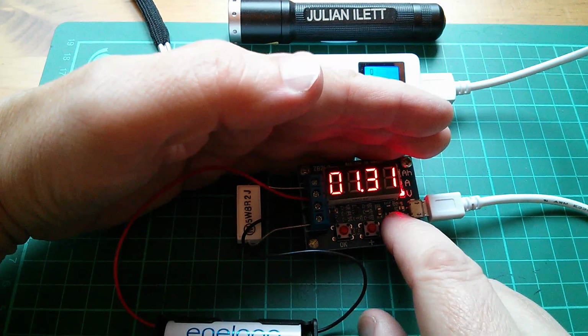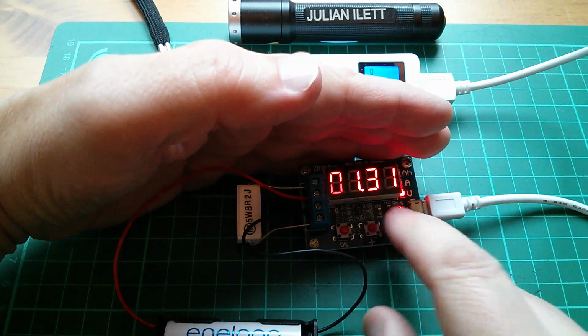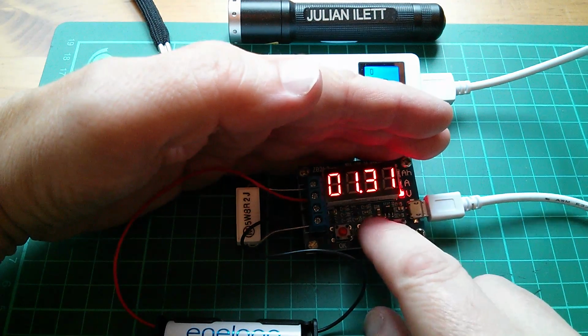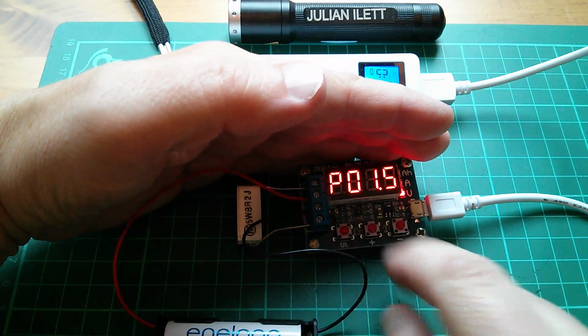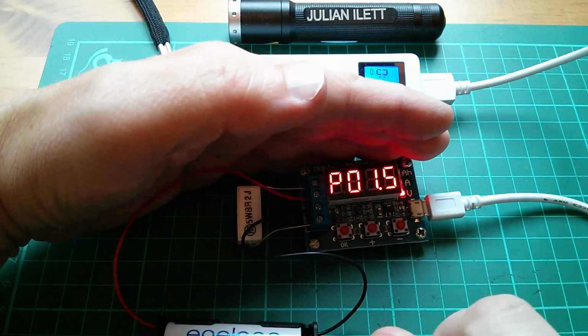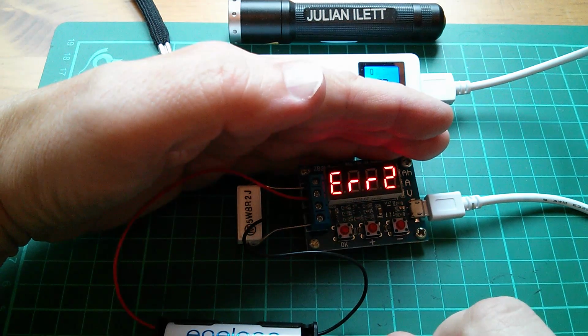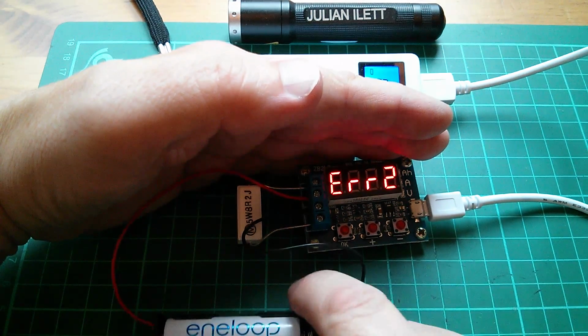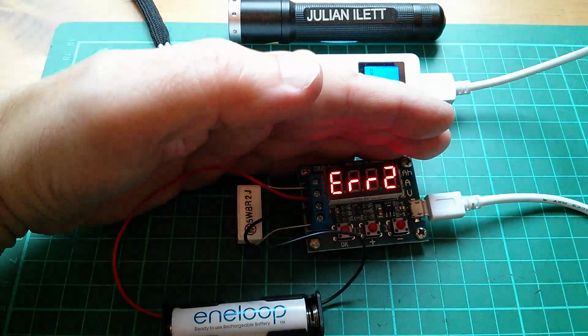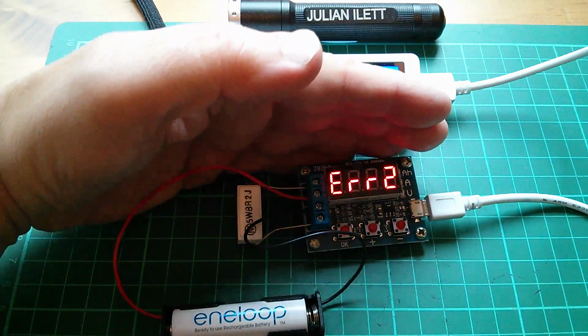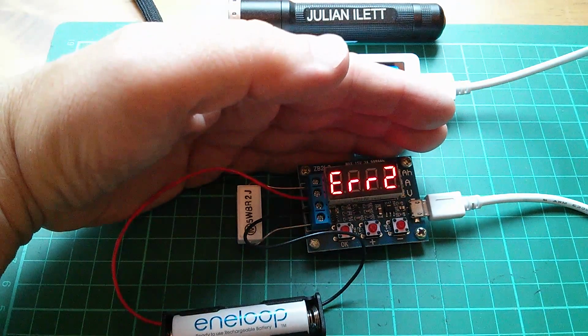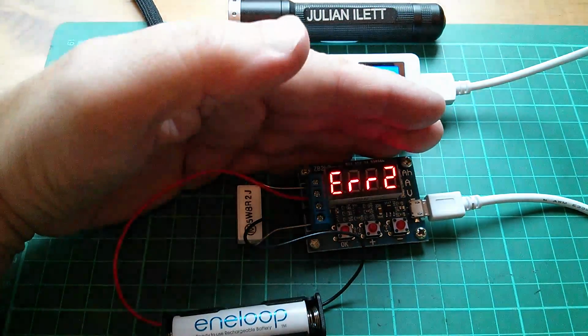But what I can do is I'm going to force an error now. It's 1.31 volts. I'm going to set the end voltage to 1.5. And it should say that's an error because the cell voltage is already below your set termination voltage. So that comes up error 2. What's that, battery voltage is lower than the setting voltage termination.